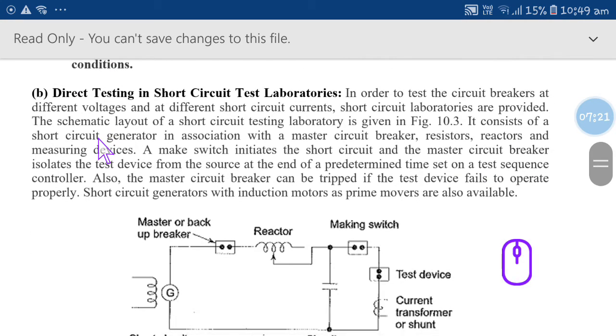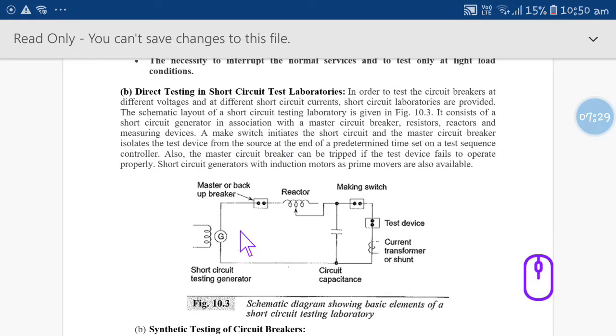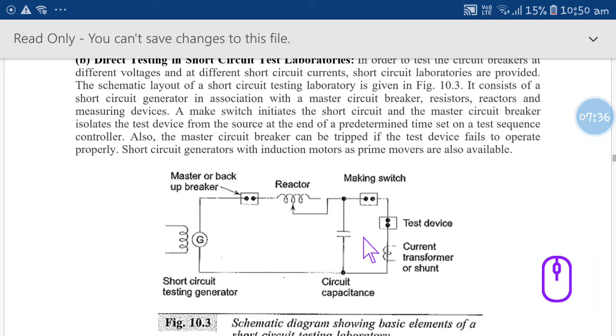In direct testing we can go for the short circuit test in the laboratory. This is very much important, it has been asked in the question paper. Just have a look at direct testing. In order to test this type of circuit breaker at different voltages, see what the schematic layout consists of. This is the schematic layout, okay. It consists of a short circuit generator, and a make switch, and a master breaker switch. It is associated with the master circuit breaker, resistors, and reactors, and measuring devices also. The make switch plays a very important role, which will initiate the short circuit, and the master circuit breaker isolates the test devices from the source, okay.